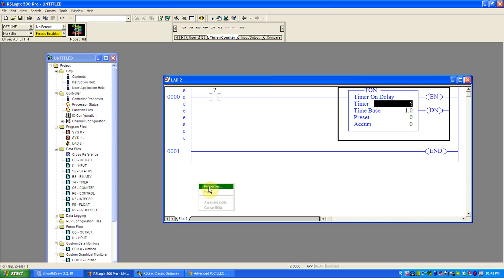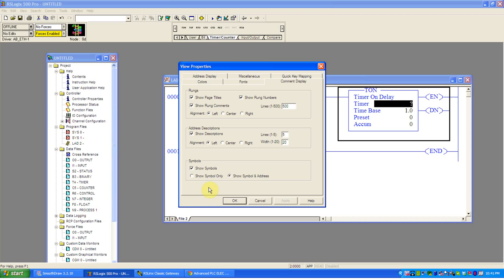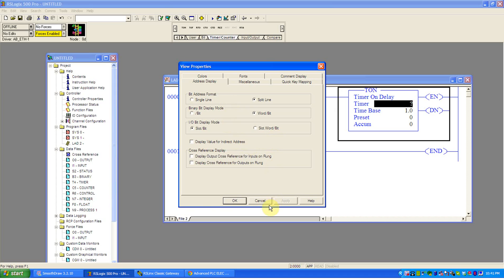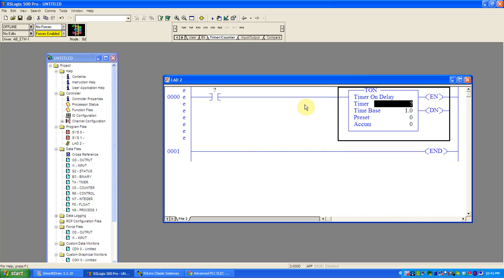People get confused on the address. But if you go right side mouse on the ladder logic and say properties, you'll see you can choose how the address is displayed. Split line, single line, slash bit or word slash bit on IO, meaning stuff that's input, output only, connects to the real world. Do I want slot bit or do I want slot word then bit? It's our choice. So people get confused. I don't understand why mine looks different than his or mine looks different than last week. It's all exactly the same. It's just how we've chosen here to have it represented in this logic here.